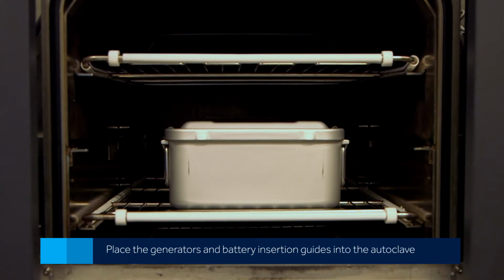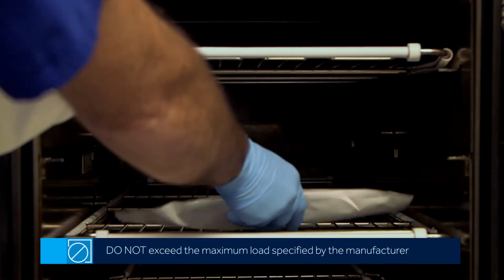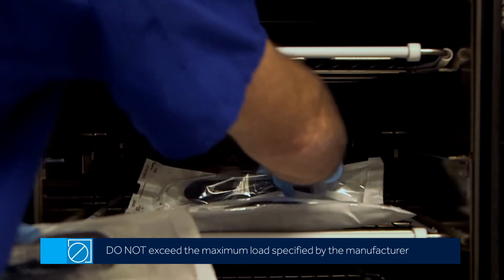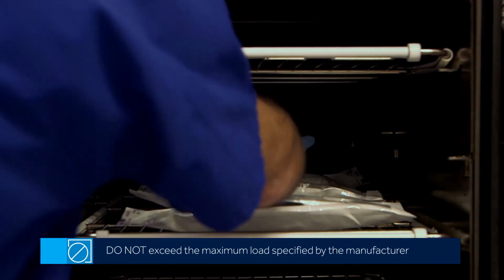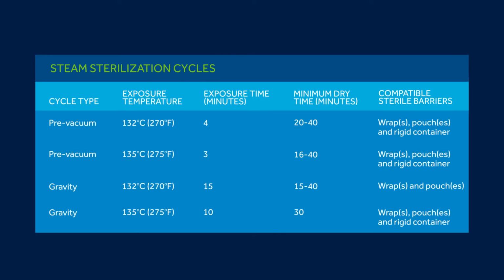Place the generators and battery insertion guides into the autoclave. Do not stack the generators and battery insertion guides. Note: when sterilizing multiple instruments in one autoclave cycle, do not exceed the maximum load specified by the manufacturer. Select one of these sterilization cycles in the Steam Sterilization Cycles table of the IFU. The minimum sterilization temperatures and times in each row of the recommended cycle parameters have been validated for achieving product sterility, and the Sonicision products have been qualified to withstand repeated exposure to the maximum temperatures and times listed.